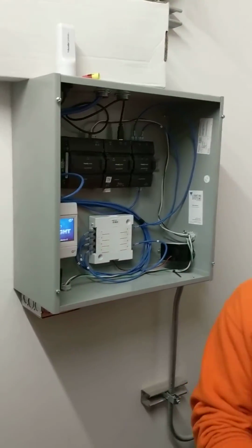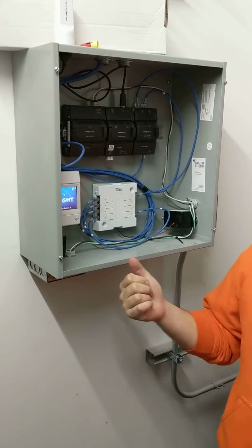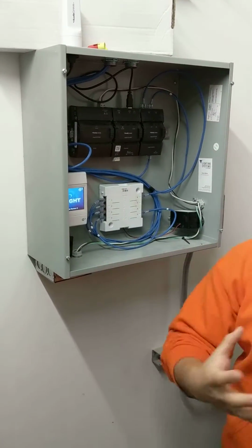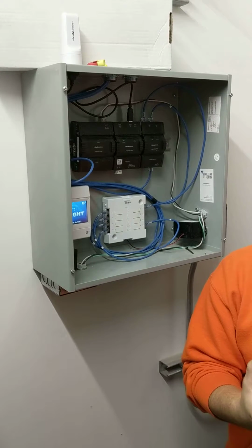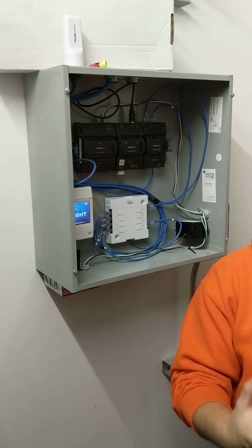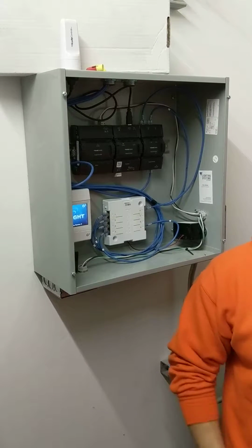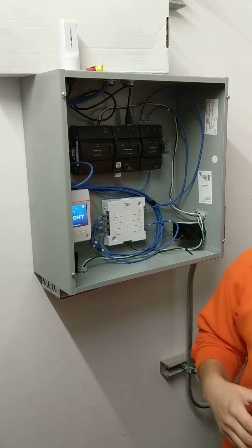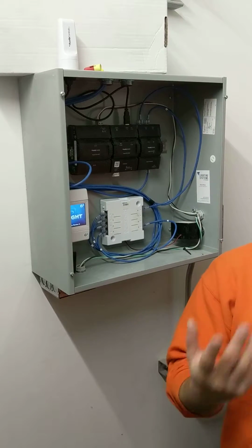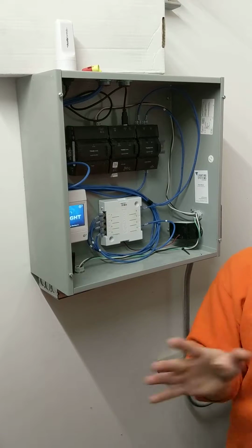What about a power outage? Will it just reset itself? Power outages themselves, all the devices have their own programming built in. They have, I believe, a 7-year shelf life without power. It's non-volatile memory. So as long as they're powered back on within 7 years, they'll retain the memory. So you can actually take stuff off, put it on the shelf, reinstall it later after renovation. It's still going to maintain its programming. So it shouldn't have any issues there.